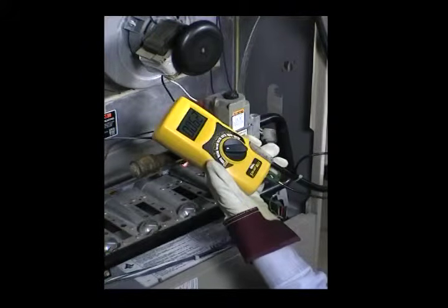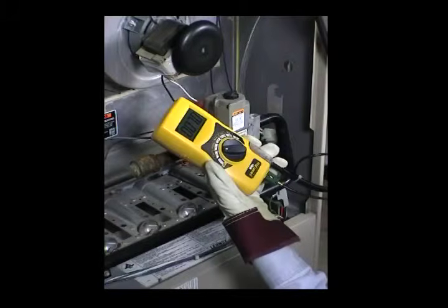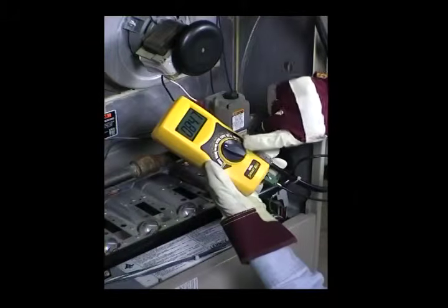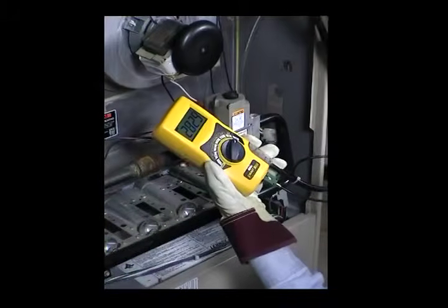So you can see the adjustments and the response in real time as it continually draws a sample and analyzes the gas. So when I know I'm in the target area, again I can verify efficiency for combustion is approximately what I expect. I can look at my flue temperature.